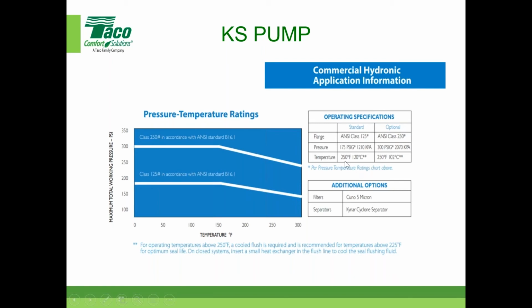And we're looking at this temperature range, 250 degrees, so I don't see an issue there in that regard. I think I actually have a mistake here. But for anything above 250 for operating temperatures, we recommend a cool flush line is required, and 225 and above. And really, that's just helping the seal, right? If it was clean water, the seals would last a very long time. John Crane is a very, very good company, and many of us pump manufacturers use them.